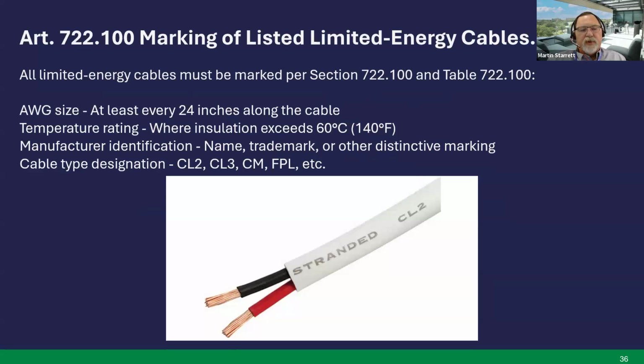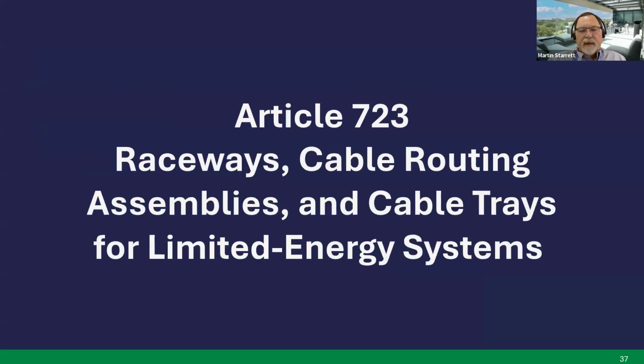An example would be 722.100, marking of listed limited energy cables. All limited energy cables must be marked per this section and table 722.100. For example, the gauge size has got to be at least every 24 inches along the cable. The temperature rating where the insulation exceeds 140 degrees Fahrenheit. Manufacturer identification, including name, trademark, or other distinctive marking, and then the cable type designation, such as CL2, CL3, CM, FPL, etc. Next slide.